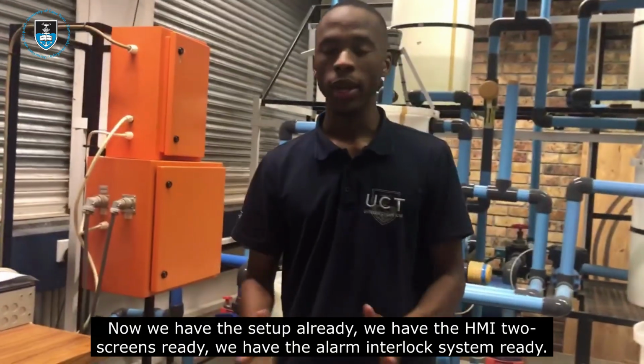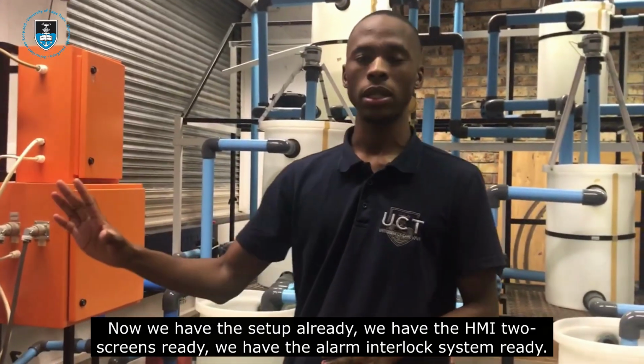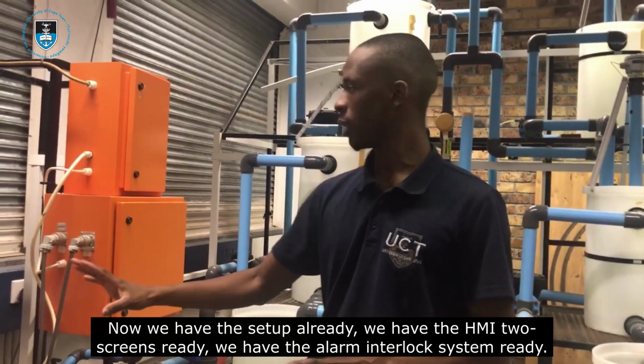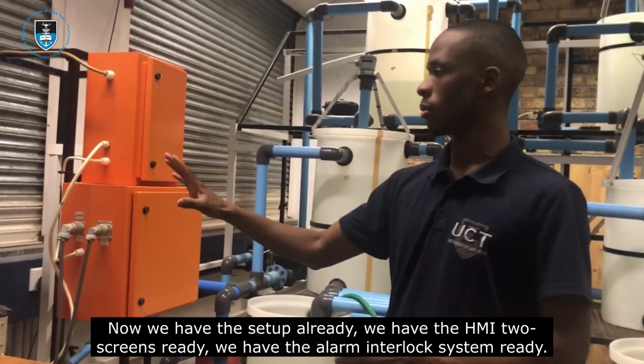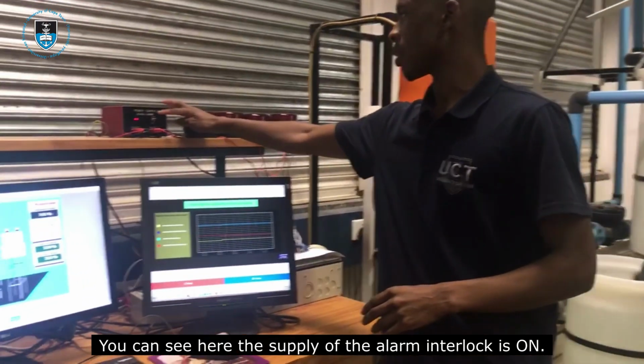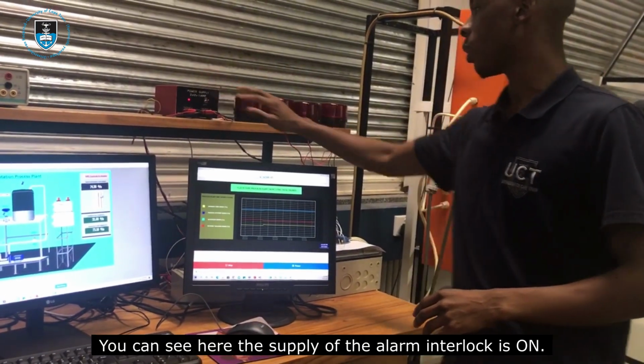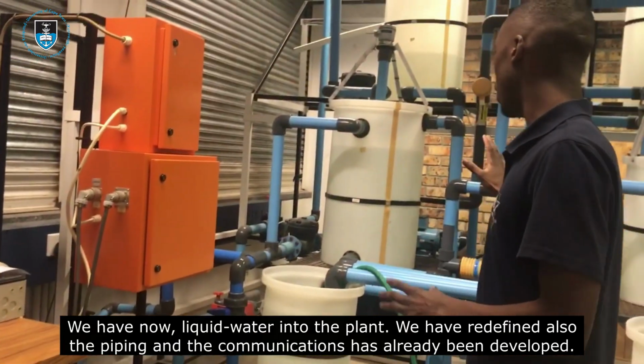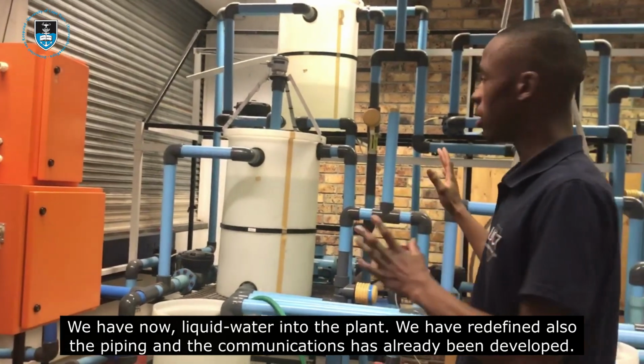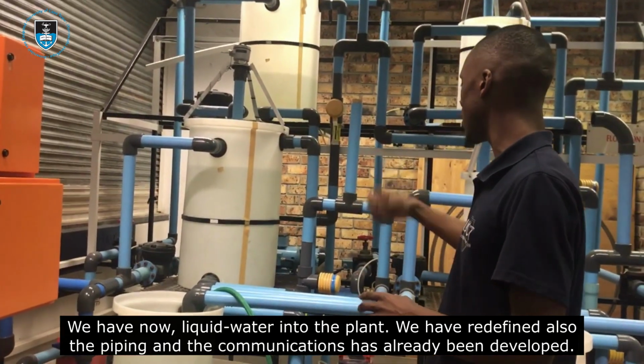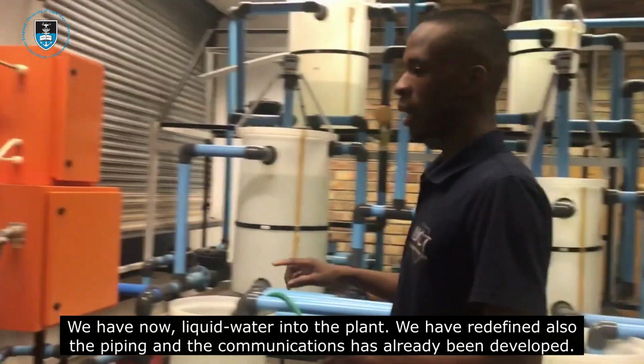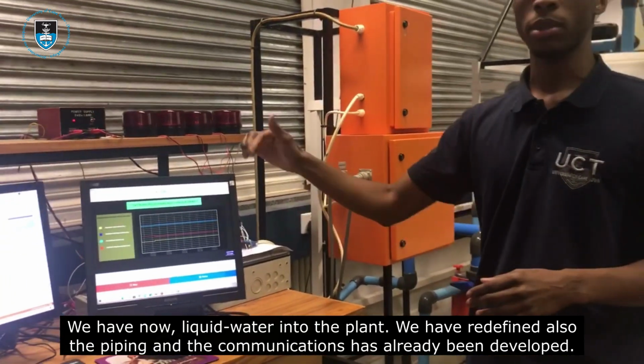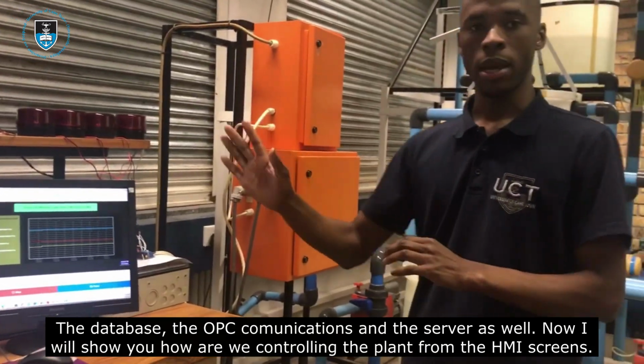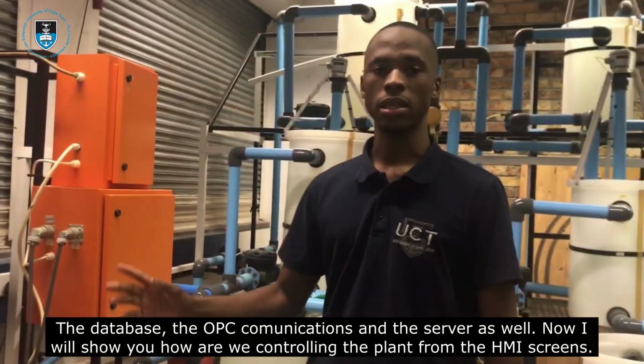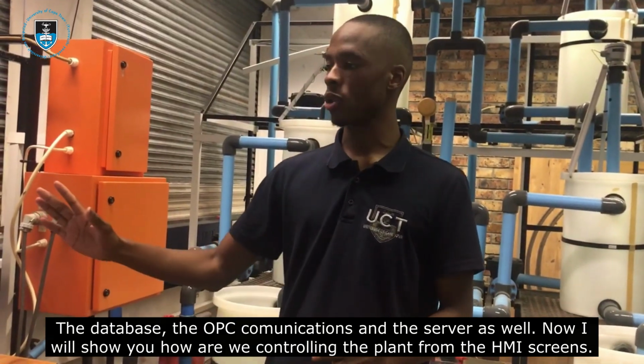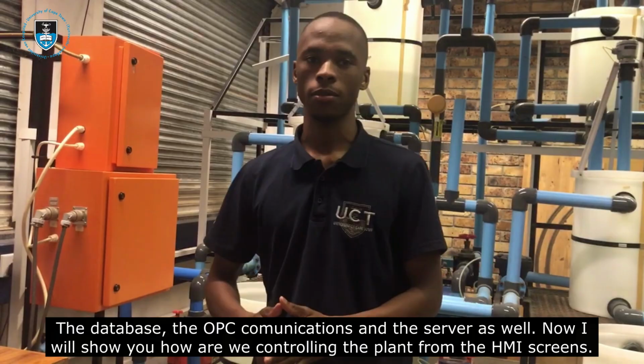Okay, so now we have the setup already. We have the two HMI screens ready. We have the alarm interlock system ready. You can see here the supply of the alarm interlock is on. We now have liquid water in the plant. We have redefined the piping, and the communications have already been developed: the database, the OPC communications, and the server as well. Now we'll show you how we're controlling the plant from the HMI screens.